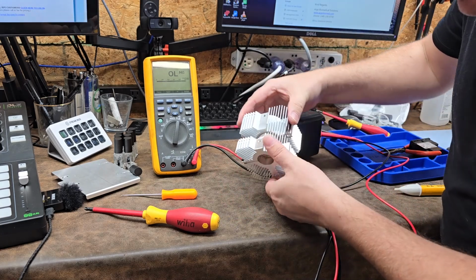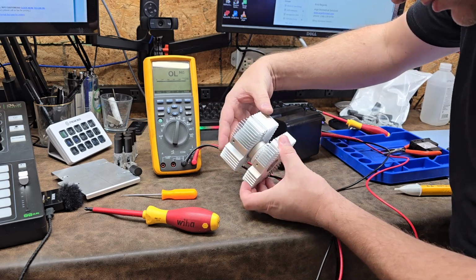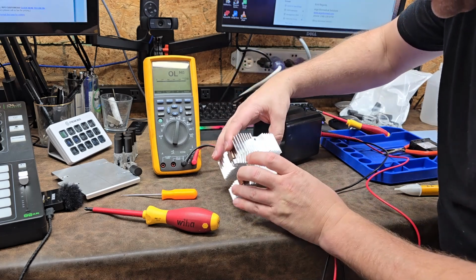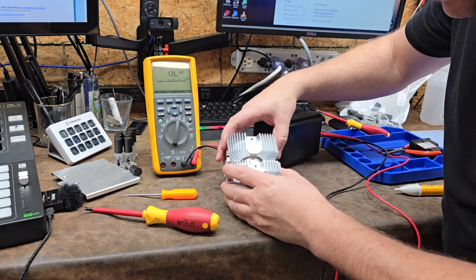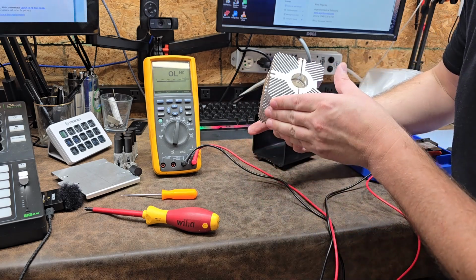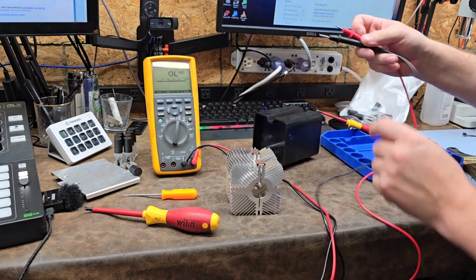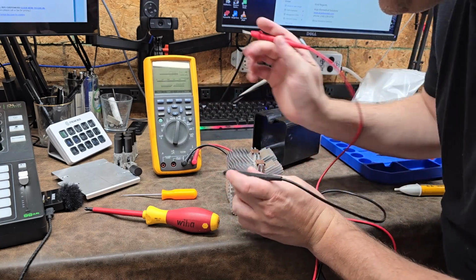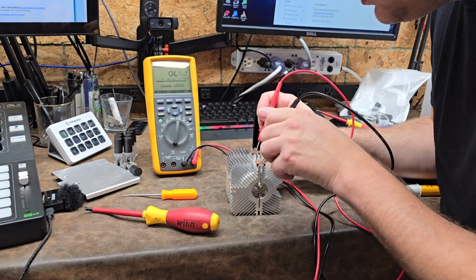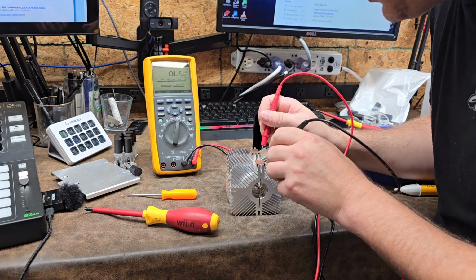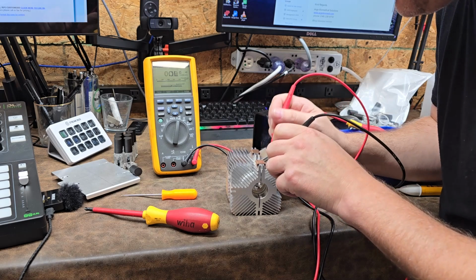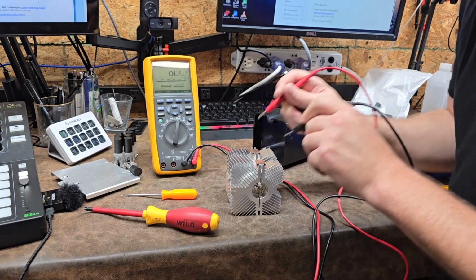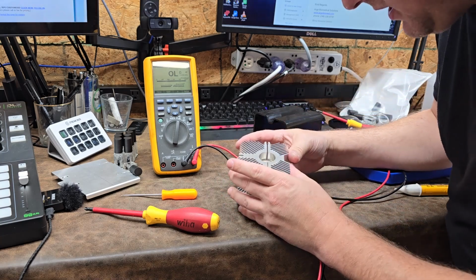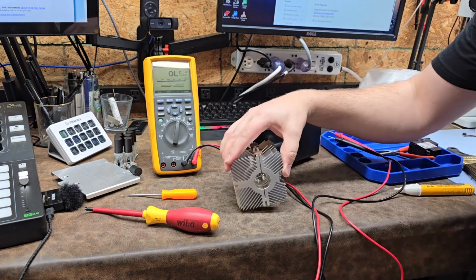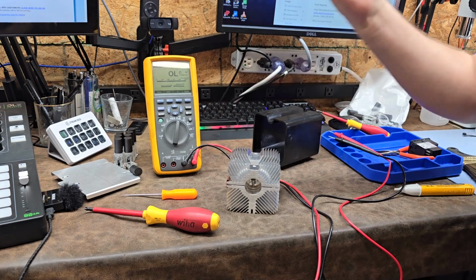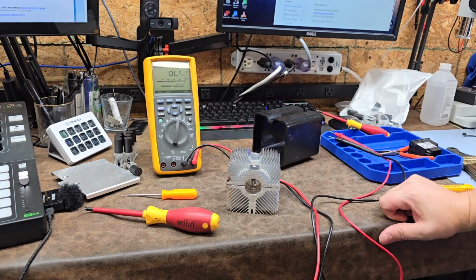That looks really clean, guys — really clean all the way around. It's got a ceramic insulator separating the two. So let's check it, we're on ohms. Okay, so there's no direct relationship between the two whatsoever. So high voltage wise, it's just arcing down inside on the parabolic, and that's why it popped the AC mains fuse. Who knew? How crazy is that?